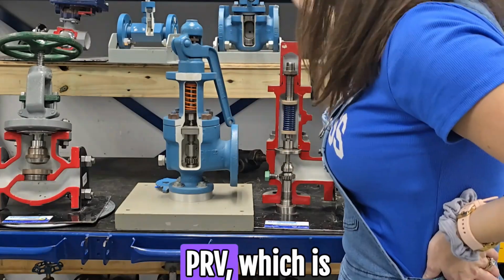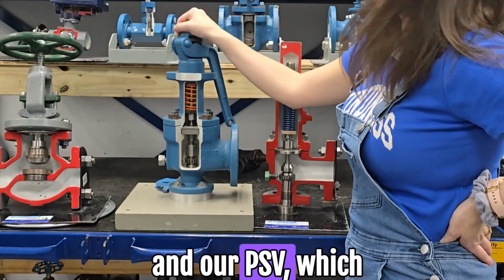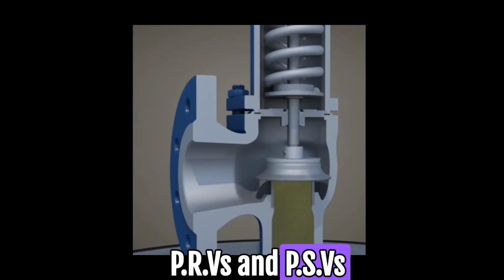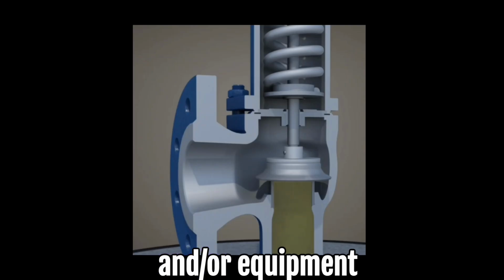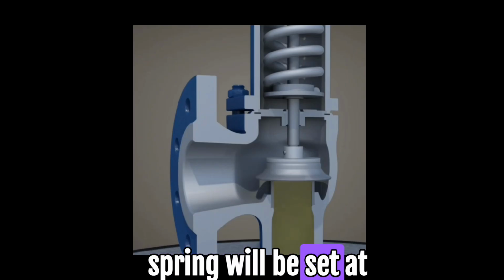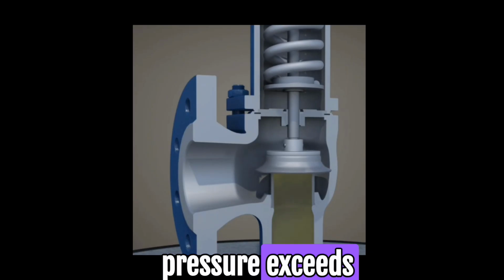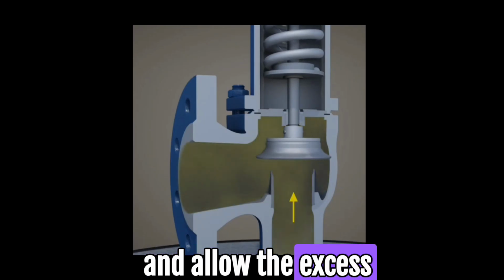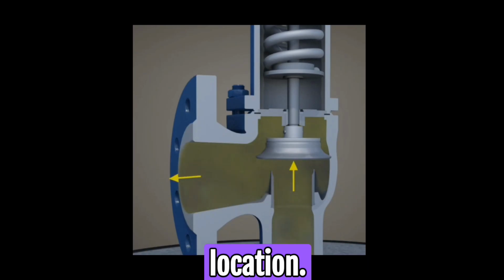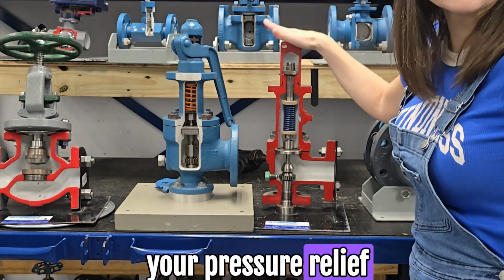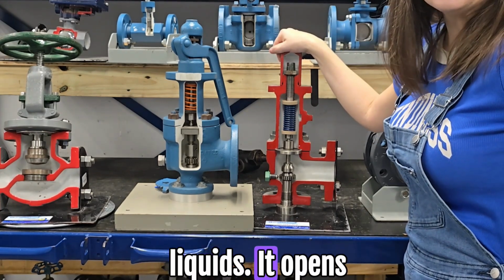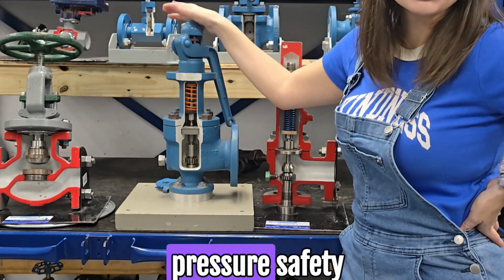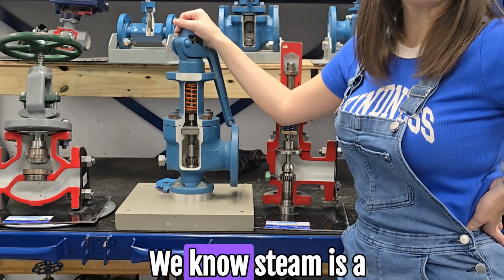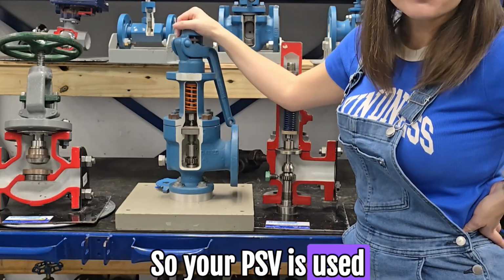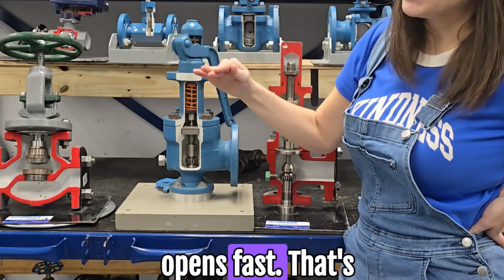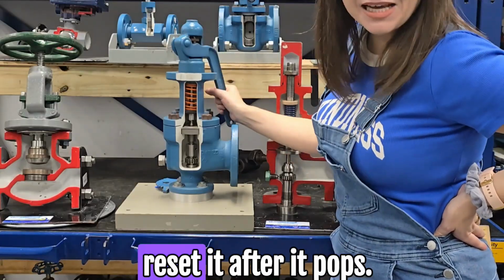Next up, we got our PRV, which is pressure relief valve, and our PSV, which is pressure safety valve. PRVs and PSVs protect process piping, vessels, and or equipment from overpressuring. The spring will be set at a specific pressure. If the process pressure exceeds that set pressure, it will lift the spring and allow the excess pressure to exit to a designated safe location. I correlate the L in relief with liquids, so your pressure relief valve is for liquids. It opens gradually. Your PSV, your pressure safety valve, I correlate the S with steam. We know steam is a vapor, right? So your PSV is used for vapors and it opens suddenly. It opens fast. That's why there's a handle on it so you could reset it after it pops.